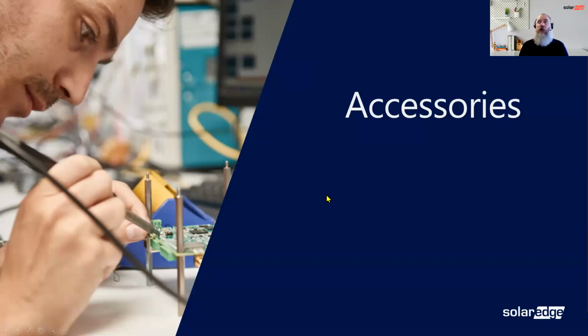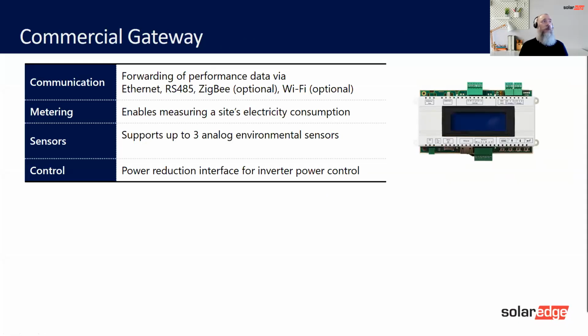Accessories, what have we got? Let's have a look. We've got the commercial gateway. This device here has the 2 RS485s at the top. This allows us to do the follower and leader and also connect to the meter. It also allows us to have sensors at the bottom. And it also allows us to do the PRI, so the power reduction interface at the top, which we showed you on the communication board.